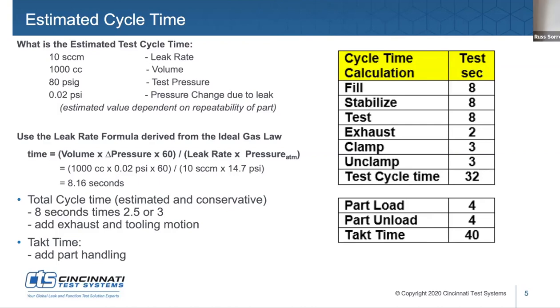Now let's go back. One of the questions that I've gotten all the time is, well, why 0.02 psi on the delta, Russ? Why does that matter? So 0.02 is a conservative factor. It's something that we found fits with absolute pressure decay testing. And we look for a 2-to-1 difference between a good part and a part that has a leak in it. And that 0.02 kind of fits that window as well. Lots of times as we use more sensitive technology that we'll talk about, differential pressure decay, you can see a lower pressure drop, and that allows us to get a faster cycle time. However, this is a good starting point for lots of applications. The majority, right?